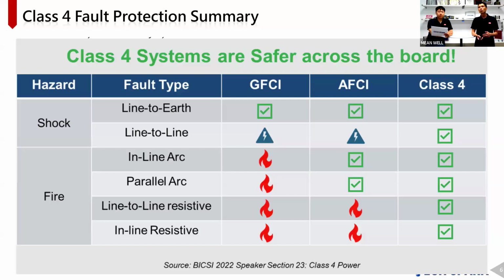That signal keeps sensing. If there is an abnormality, it basically shuts down the whole system to make it safe. And so once it's proved to be safe, then it does not require conduit. The whole thing is you don't have conduit to do the installation. So it can transmit at high voltage, long distances, very high power, but the safety requirements are even more relaxed than or the same as a class 2. Like you don't need an electrician, you don't need conduits.